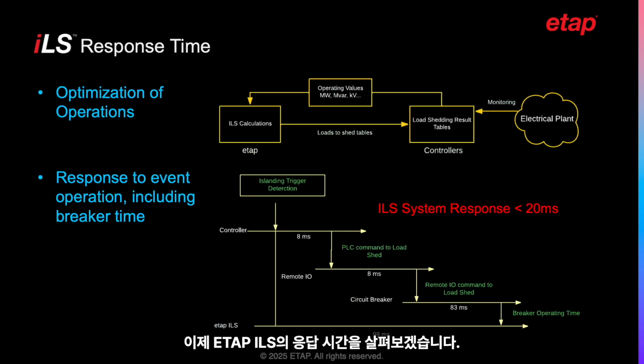Now let's look at the ETAP ILS response time. Under transient conditions, the operation is within 20 milliseconds on average. In some systems, 6 milliseconds response time has been achieved. For a steady-state operation, the response time is controlled and configurable depending on the disturbance type and location.